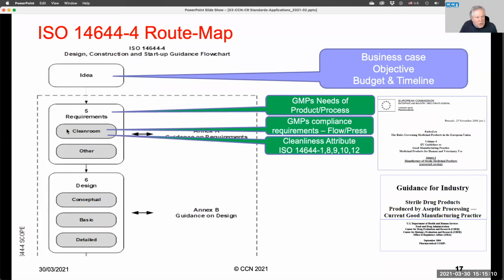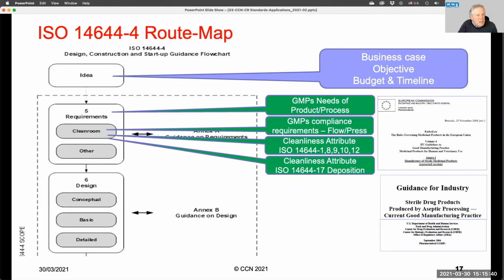Then we need to employ, during this requirement stage, appropriate reference to the cleanliness attribute. And remember, that could come from parts 1, 8, 9, 10, or 12. All of those express cleanliness attributes in the clean room or clean air device. If it's a life science application, we're looking at part 1 for airborne particles. We might have another attribute of particle deposition rate. Right? So that's another attribute of cleanliness that we might add to the mix. So it might be that my particular process says that I'm really concerned about, in my micromechanical, making my gyroscope or my optical system or my inkjet cartridge, particles depositing on the product or process. So I might introduce that as a specification attribute of my clean room.